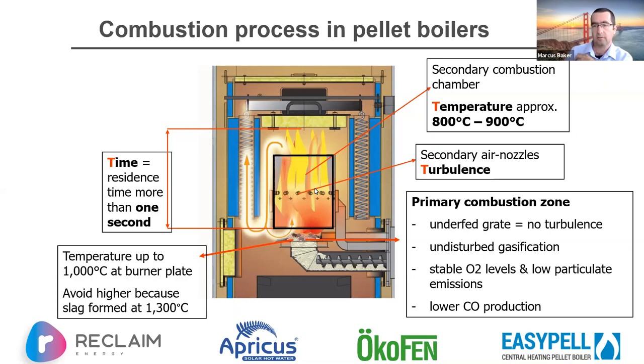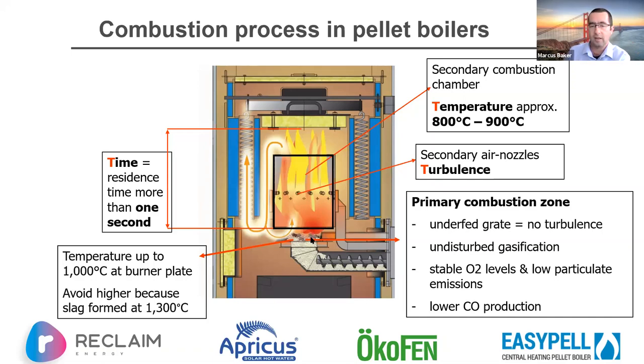Moving up into the secondary combustion zone, air is fed all the way around — it's essentially a big ring — and blasted up. You want lots of turbulence here. Just as if you've had a fire at camp and you fiddle with it a lot, it doesn't burn very well. You want a nice stable bed of embers, but up here you want to introduce as much oxygen as possible in the most fluid way to get really good secondary combustion, reaching much higher temperatures.